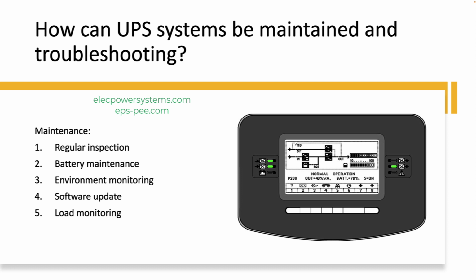Environment monitoring. Ensure that the UPS system is installed in a suitable environment with proper ventilation, temperature control, and protection against dust, moisture, and excessive heat. Software updates. If the UPS system has associated software or firmware, keep it updated to ensure compatibility, bug fixes, and improved functionality. Load monitoring. Regularly monitor the load capacity of the UPS system to ensure it is not overloaded, as this can lead to reduced backup time and potential system failures.